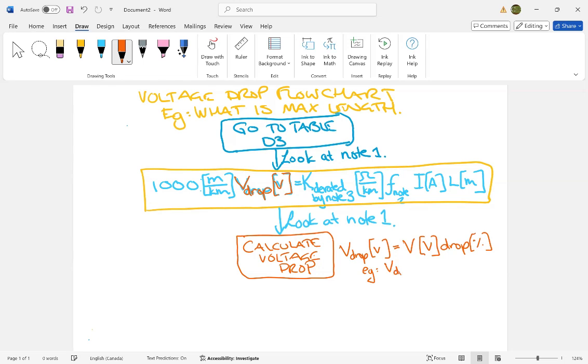Voltage drop is going to be equal to 120 volts times, let's say you want a drop of 2%, it would be 0.02. That's just an example for you. Okay, so you put your drop into, you put your percent into a decimal format, okay, and that's the voltage that you're going to use. It's going to be your voltage times that percent in decimal format.